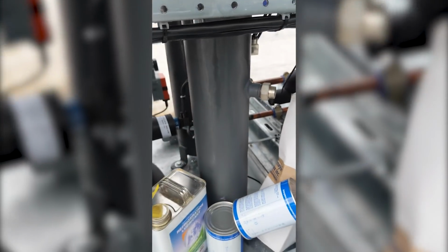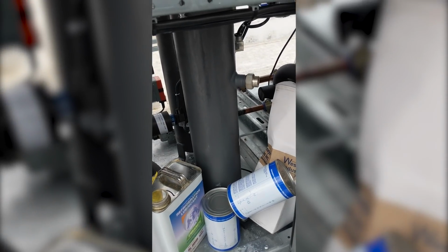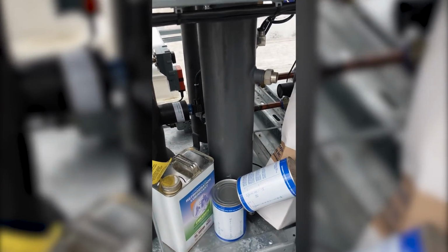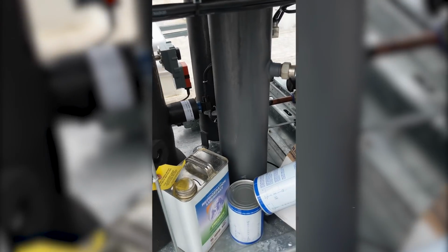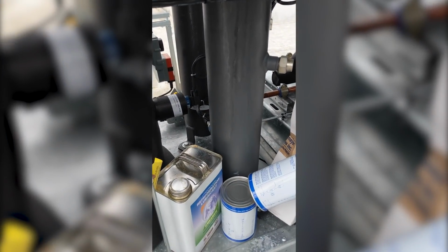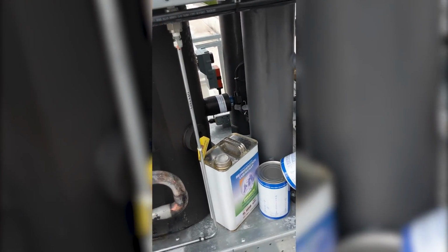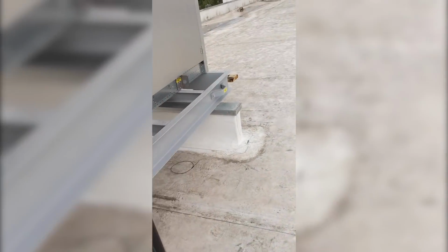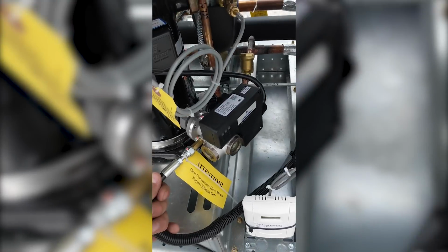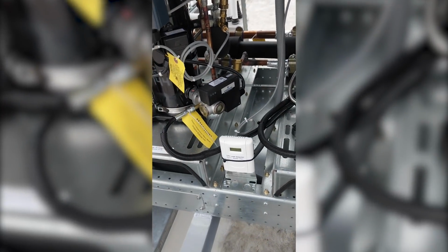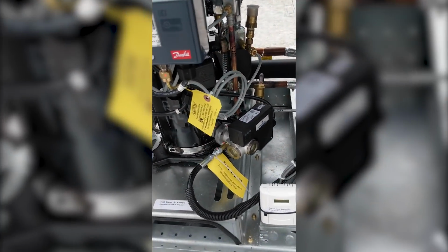This reservoir tank is always maintained at 500 pounds. It's 100 pounds over the medium temp scrolls, and it's 300 pounds over the low temp scrolls. So that way it can push oil into the compressor controls, the OMC controllers. So this line always has 500 pounds of oil on it. So we have plenty of oil pressure to go in here.